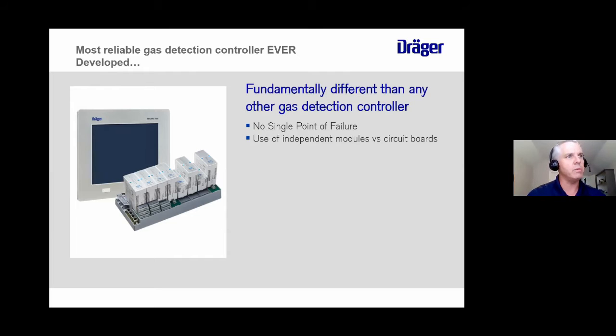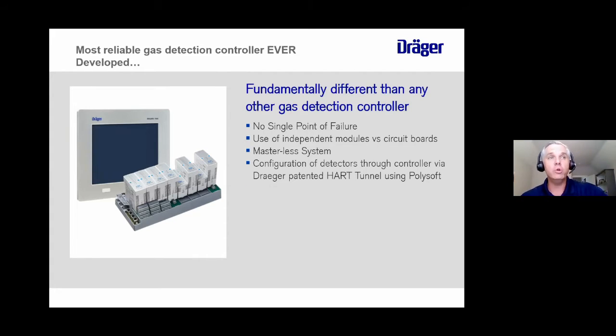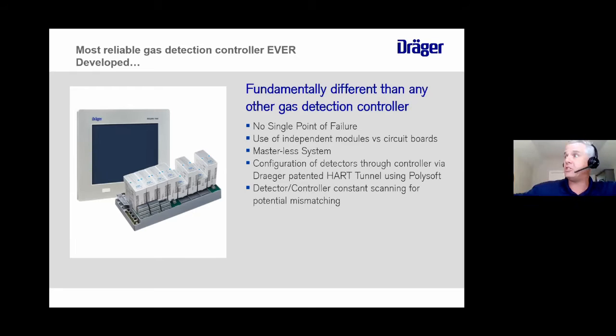So by safety system, what am I talking about? I'm talking about the modules and the visualization of that system. So even if you lose a module, you haven't lost your whole system. Another very key design feature is that it's also a masterless system. So when you first plug this thing in, no matter how many modules it has, the system will select a master that controls the function of the whole system. It's constantly scanning to make sure that whatever the ranges are at the detectors are also what the controller is seeing, so you don't have an unsafe situation.